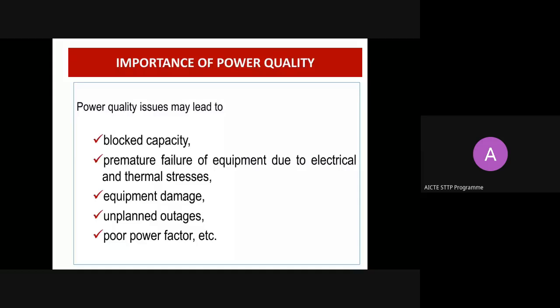Suppose the transformer was designed to serve its purpose for 25 years. Suppose, because of an industry present in the particular area which produces more harmonics, more harmonic current and harmonic voltage are passed through the power transformer. What will happen? The transformer is designed for 25 years, but it will fail before 25 years. It may fail at the 10th or 11th year, all because of the presence of harmonics in the system. So the premature failure is all because of the power quality.